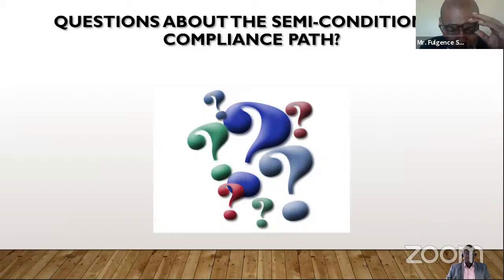How do new energy efficient buildings differ from older efficient buildings? Right, that's a good question. So the older efficient buildings, they emphasized a lot on the design. So you'll notice that, for example, the roof would be the high albedo roofs. And they would also include some degree of ventilation for the roofs in the older buildings. The newer efficient buildings have incorporated the whole idea of controls. And that's a mandatory requirement of the code.